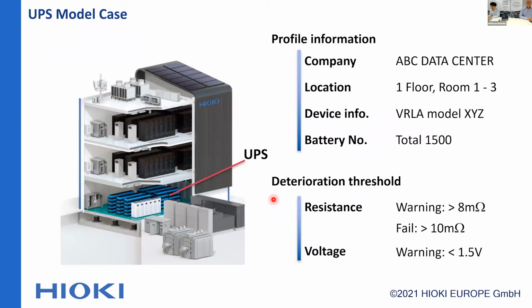Here is a company called ABC Data Centers. They now have 1,500 batteries installed in their UPS room. The maintenance company needs to make sure the resistance and voltages of the batteries are within threshold, and must create a report on which batteries need to be replaced. They need to find the deteriorated batteries, and an important part of data management is to link the measurement result with location information, like this.